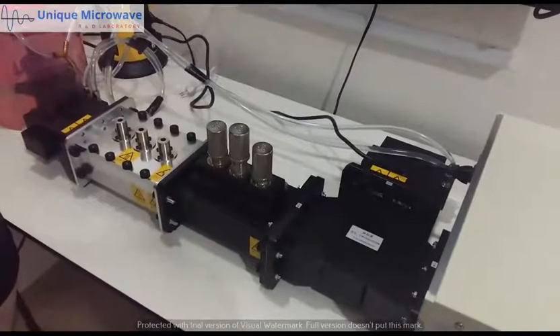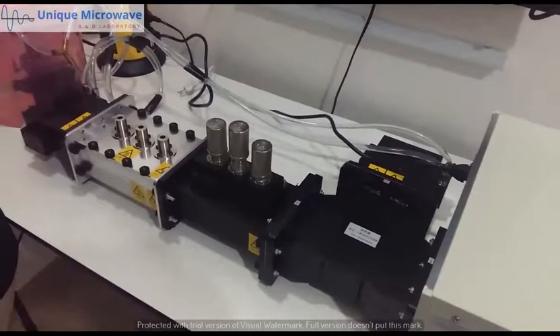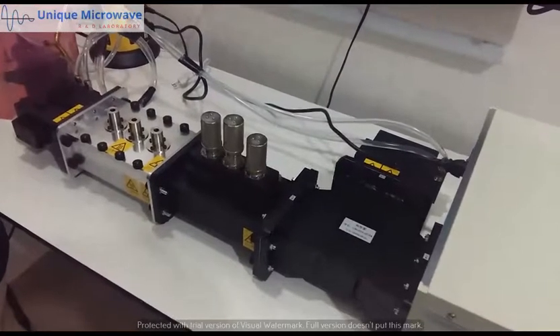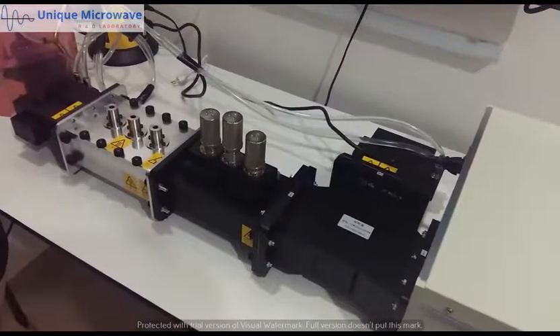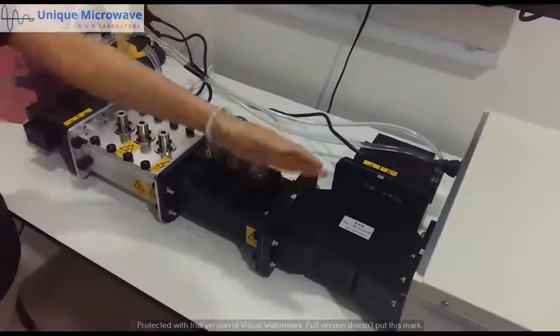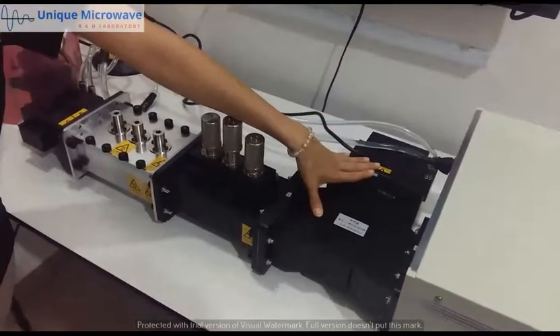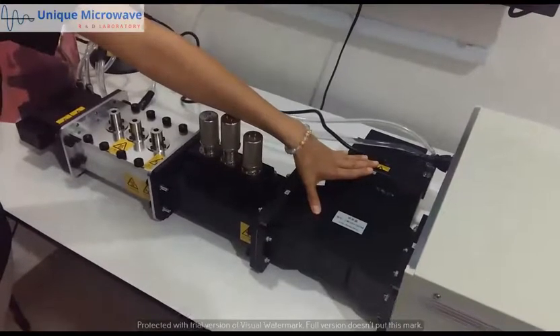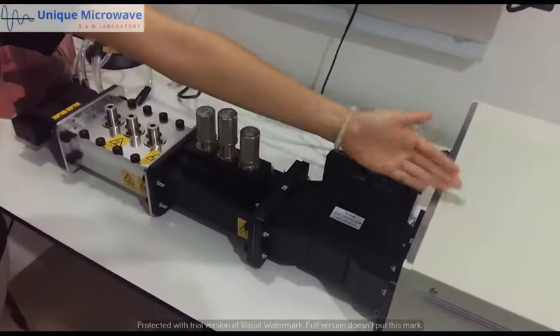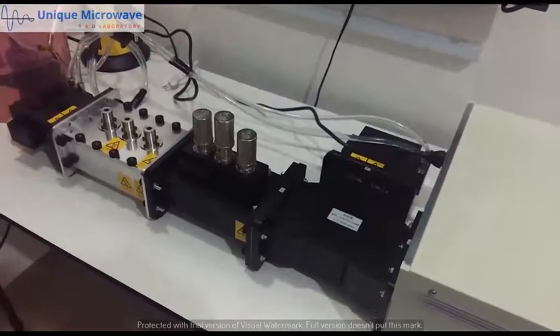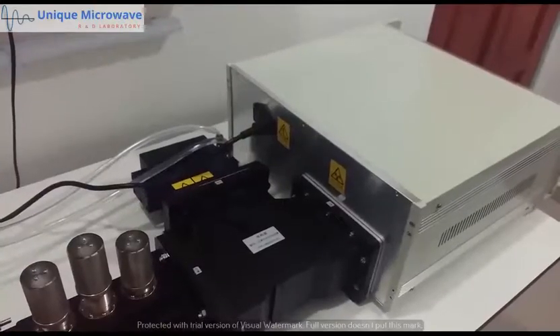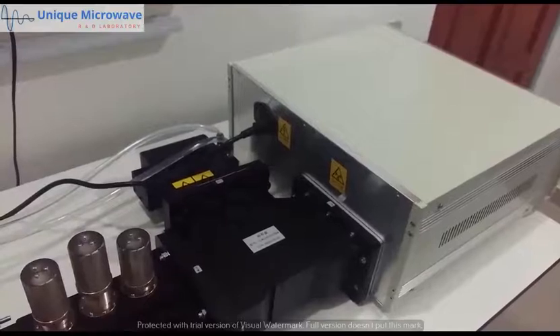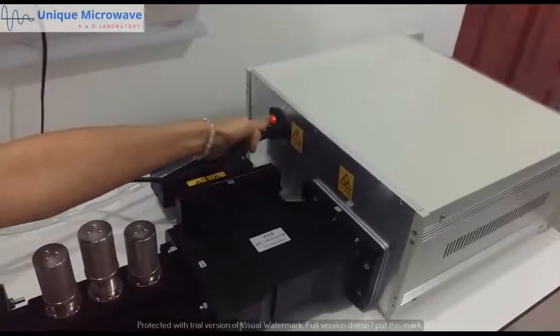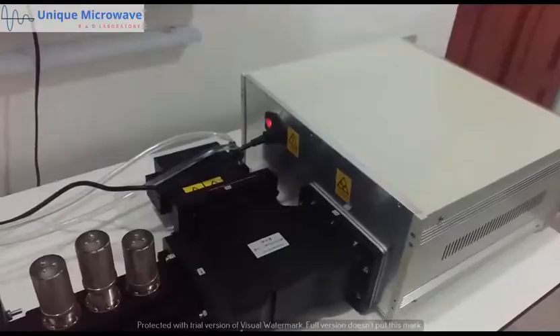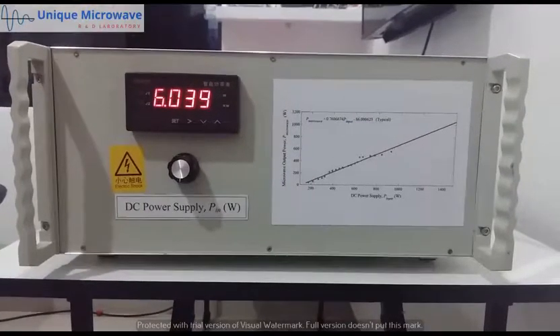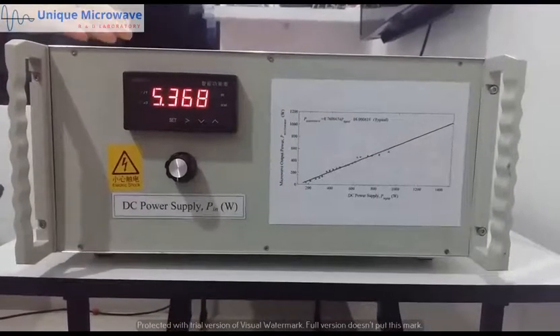Once the cavity coupling matching calibration is completed, we will remove the waveguide coaxial adapter and VNA. Then we will connect the generator, and this port will act as an isolator to prevent the reflected wave from going back to the signal generator. Now we will switch on the generator. As you can see, this is the microwave generator station.